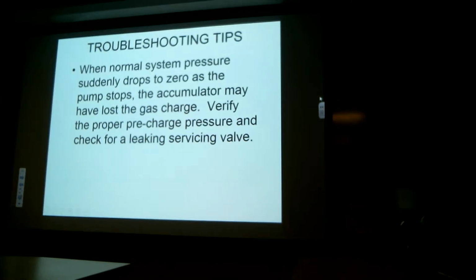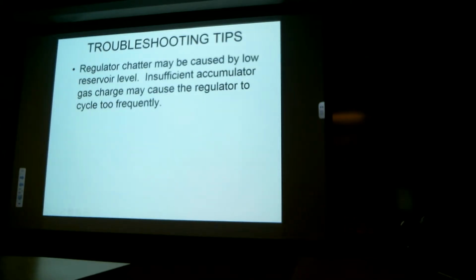The accumulator serves a function of supplementing the pump under peak load. So again, if there's no stable or at least additional pressure after the pump is cut off, it may be that the gas charge has been removed or at least lost out of the accumulator. Regulator chatter caused by low reservoir level. What's happening is the symptom is going to be present in the regulator, but the problem might be something else. In this case, insufficient gas charge in the accumulator.